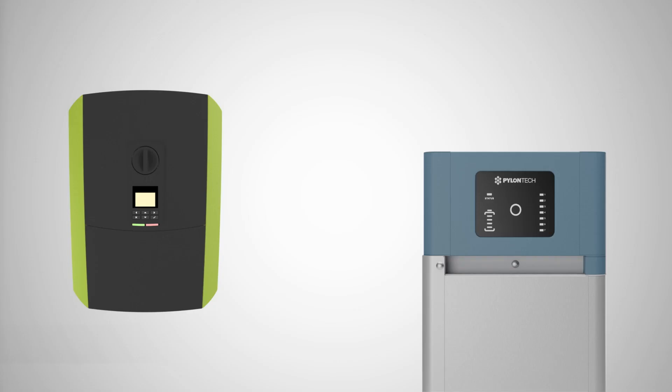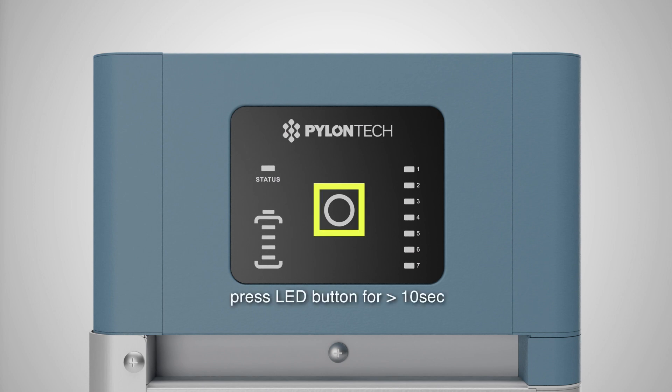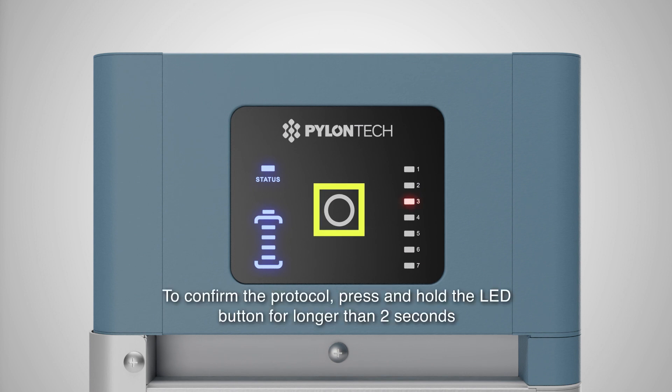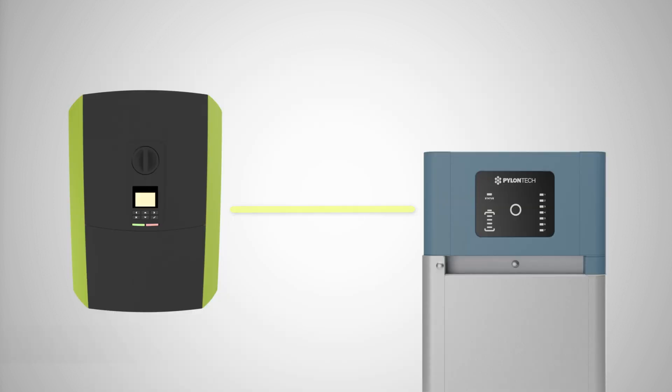The last step is to set up the communication interface between the PlentiCore and Pylontech Force H. Activate the display by briefly touching it, then press and hold the LED button on the battery management module for 10 seconds. Select the PlentiCore protocol by briefly pressing the LED button three times, then hold the button for longer than two seconds to confirm the protocol. The communication between PlentiCore and Pylontech Force H is now permanently set up and activated.